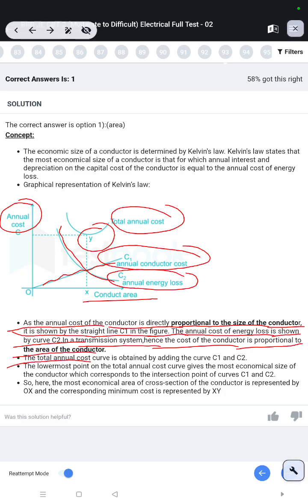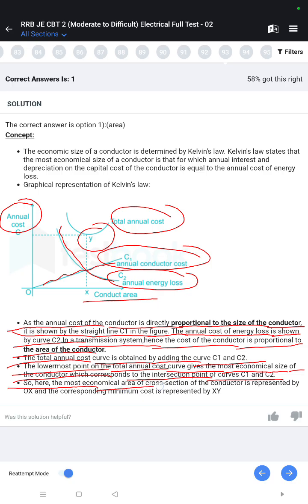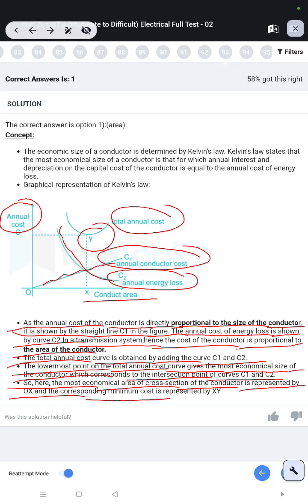The total annual cost curve is obtained by adding the curves C1 and C2. The lowermost point on the total annual cost curve gives the most economical size of the conductor, which corresponds to the intersection point of curves C1 and C2. So here the most economical area of cross section of the conductor is represented by OX, and the corresponding minimum cost is represented by XY.